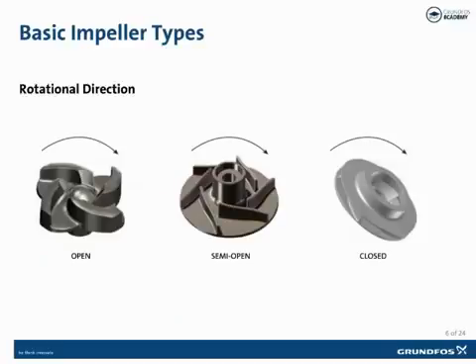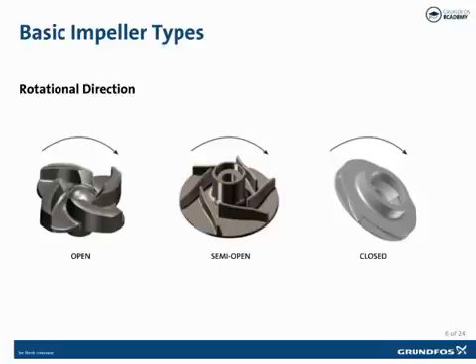The first major component we talked about was the volute. The second major pump component is the impeller. There are three common types of impellers associated with centrifugal pumps: open, semi-open, and closed. Open and semi-open types are most often used when solids are present in the liquid — let's hope that the closed-loop HVAC systems we design will not have this attribute. A closed-type impeller is also more expensive to manufacture. In most HVAC applications, high efficiency and the ability to trim are desirable, so we select pumps which utilize a closed impeller design.